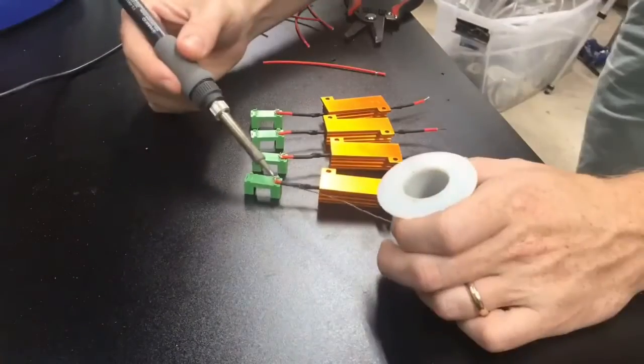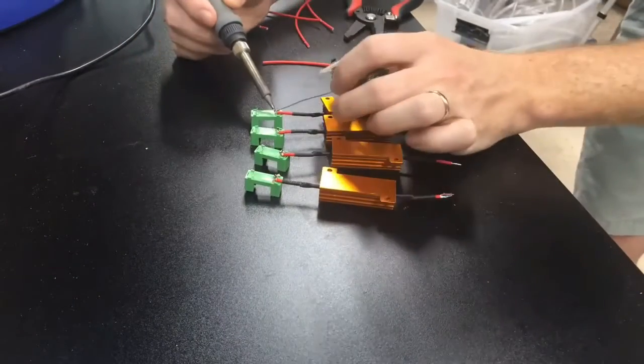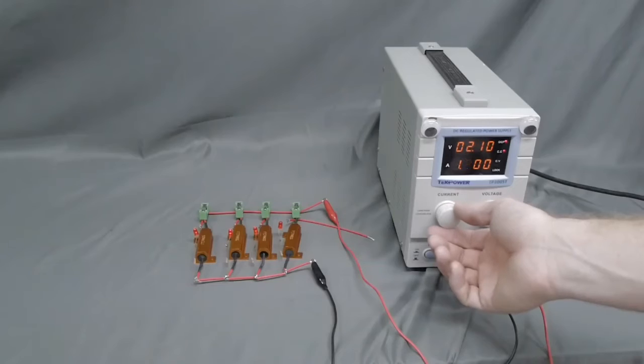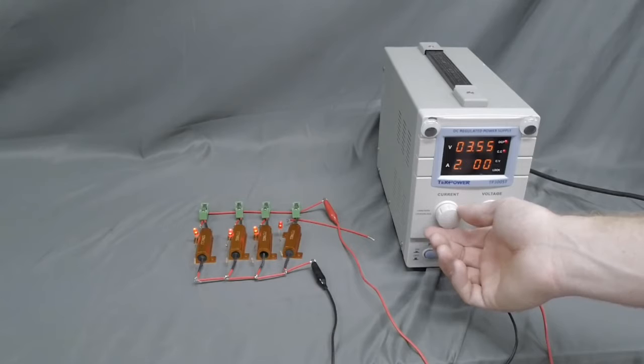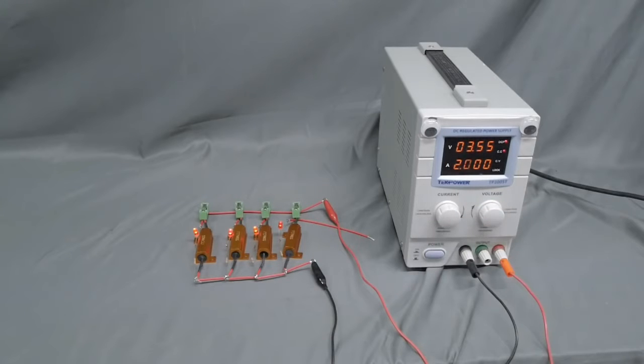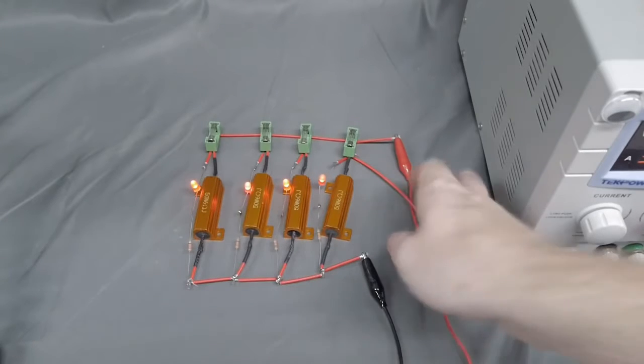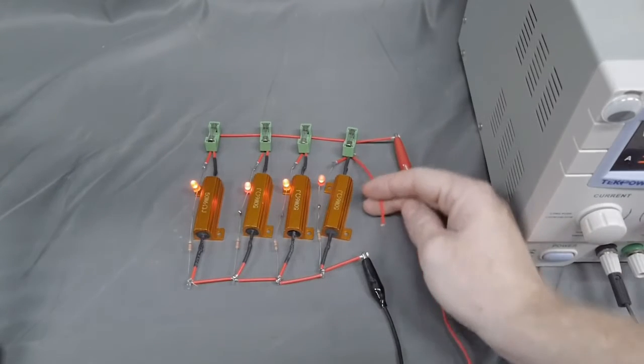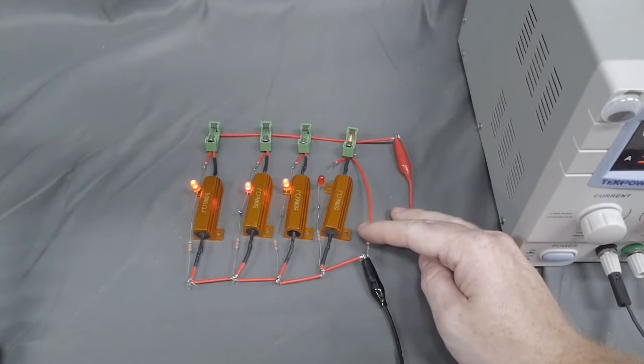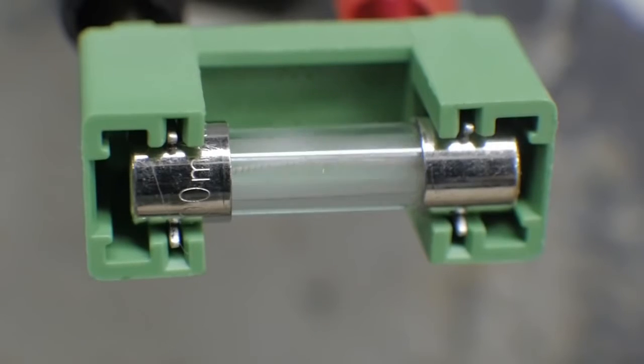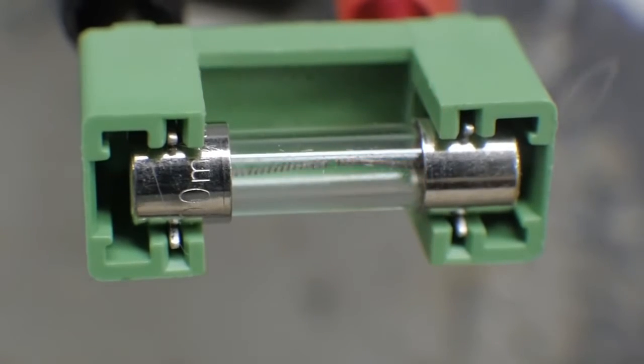But there are cases when isolation of equipment can actually make things worse, and I built a little demo to show how this works. Imagine a series of interconnected transmission lines, all feeding their own service areas, represented by the power resistor and LED light in this model. During peak demand, these lines might be operating at nearly their maximum capacity. If one line experiences a fault, for example shorting out against a tree branch, protective relays will isolate the line. In my case, when I short out the line, the fuse blows.